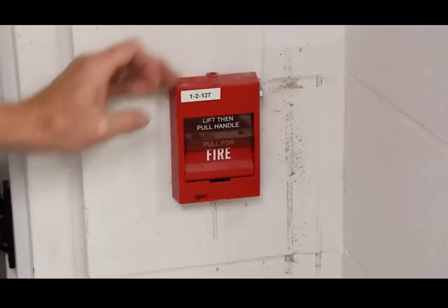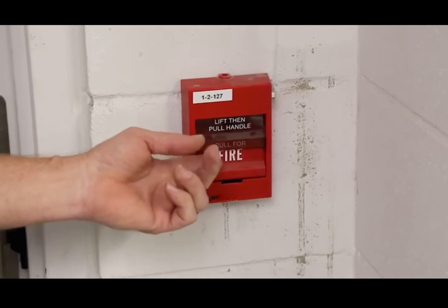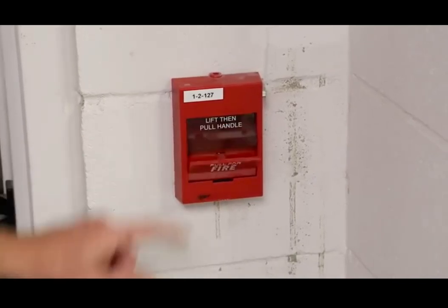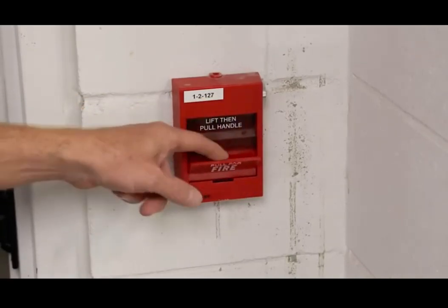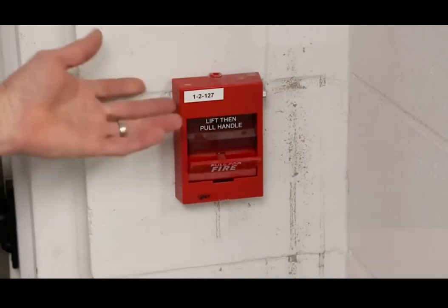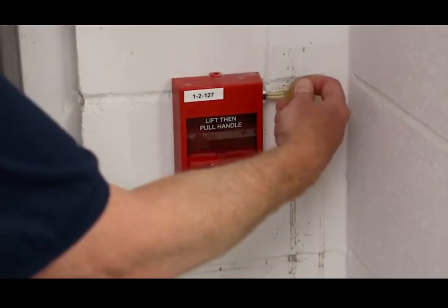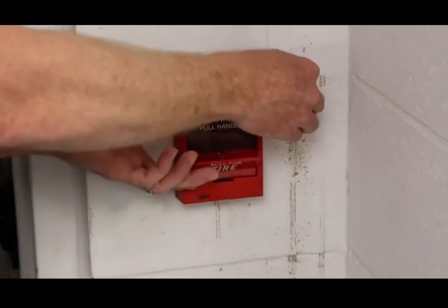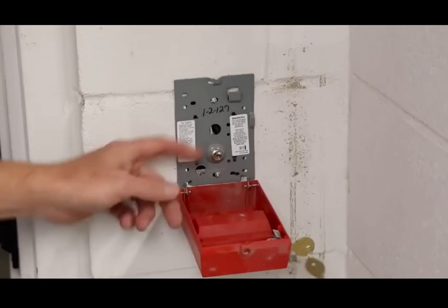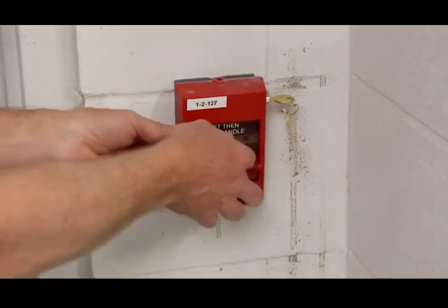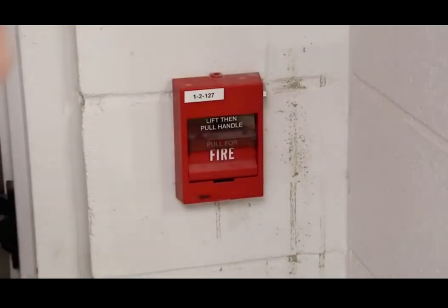All right, pull stations. Basically, we have the address label we're talking about right here for the device number. If the pull station is tripped, you'll basically see the handle sticking out like this. Okay. If the handle's sticking out like that, you can come and see it and it'll actually tell you the location of it. You can confirm the address. To reset it, remember the panel will not reset when the pull station is active. You have to reset the pull station first. Just stick the key in it, open it up, flip your switch back down, reorient the cover, just shut it back up, and then go ahead and reset the panel.